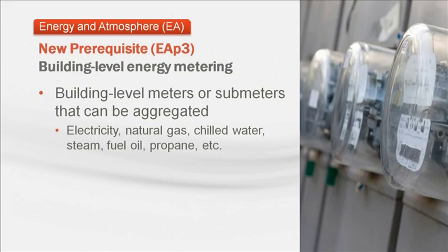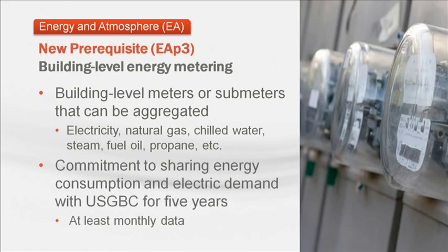For electricity, energy use in kilowatt hours and demand in kW must both be tracked. Also, at least monthly energy data must be tracked, and the data shared with USGBC for all energy uses plus electric demand. And this must be done for 5 years.